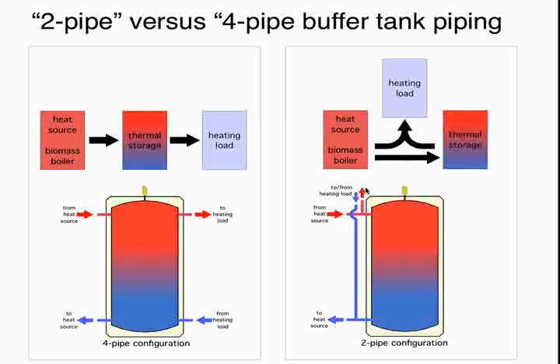So we have heat being generated from a heat source. Some of that heat can flow up to the heating load. You can see that actually better up above here. There's a possibility that if the heat source is generating heat at the same rate that the load is requiring heat, this would be the path that heat would flow. None of the heat has to go into storage. That's kind of a unique detail that is different from over here. In this case, we're passing all our heat through storage. Okay? If we had a situation where the heating load was, let's say, half of the rate of the heat source generation rate, well, half of that heat source generation would go to the load, the other half would flow into storage.